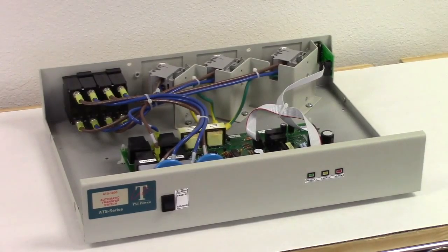This is a brief introduction to the ATS 1000 series of automatic transfer switches that are designed for applications where two or more autonomous power sources are available. The ATS can be utilized as single or multiple units for different levels of redundancy. ATS switches power sources in less than 8 milliseconds. This exceeds ITIC's CBEMA curve requirements. ATS operation is silent as there are no internal fans.